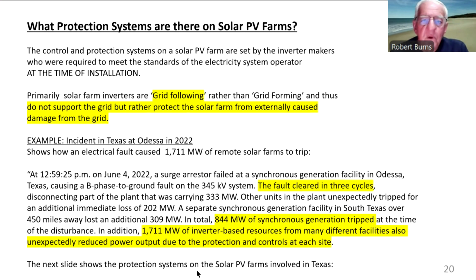So why did the solar farms trip? And where did these oscillations come from? Well, the solar PV farms, of course, the protection systems and control systems are generally set by the inverter makers who meet whatever the standards are required at the time of installation. And if you know our market here, AEMO keeps changing the rules and making things more stringent and harder and so on. So I'm sure that happened over there too. Importantly, the solar farms have inverters to convert the DC supply to AC, but they're grid following, not grid forming. And thus they do not support the grid, but rather they protect the solar farm from externally caused damage from the grid.